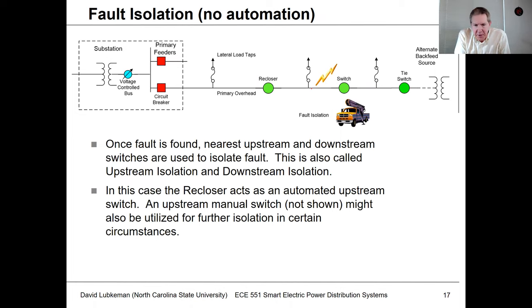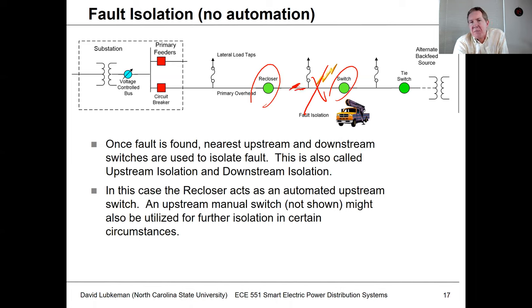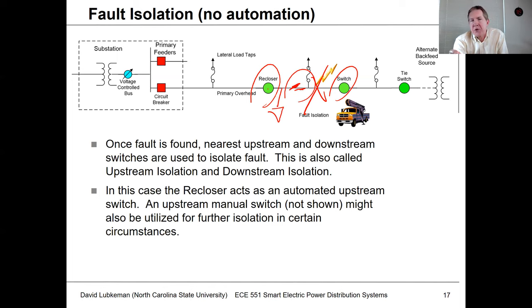For fault isolation — once I know where the fault is, say within a section, I'd at least have to have the upstream switch open. If I have a recloser, that happens automatically. If I'm going to be back feeding, I also need to operate a downstream switch. I might have other manual switches I'd want to use as well — for example, opening a manual upstream switch so I can close in the recloser to get a few more loads back online. The goal is to make the fault section as small as possible.